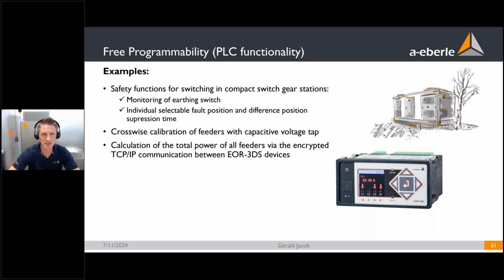One example I mentioned already is the switching functionality. By the switching functionality, for example, the earthing switch is monitored. The earthing switch must be switched off so that the load breaking switch can be switched in. So there's an additional security feature, and there are some other special functionalities implemented this way.